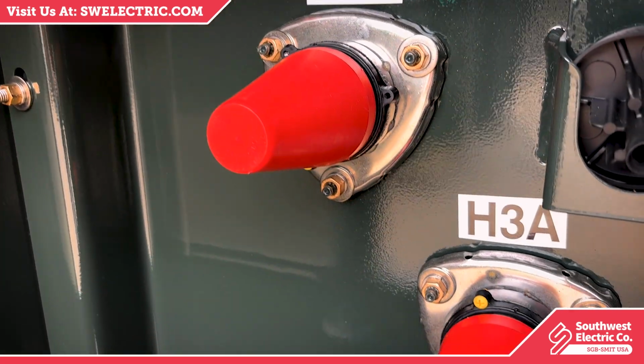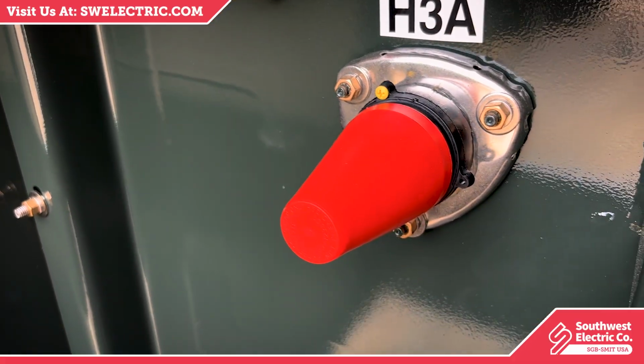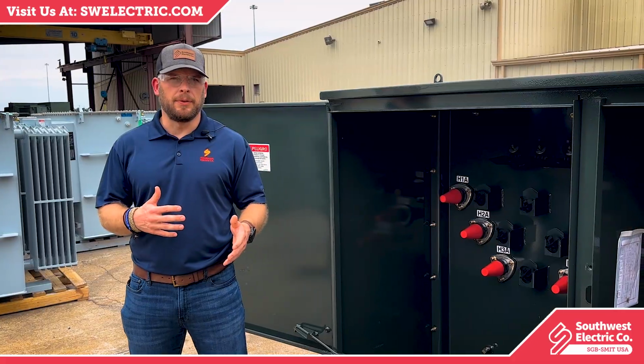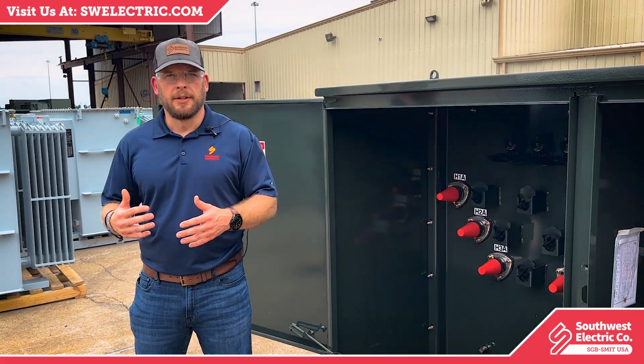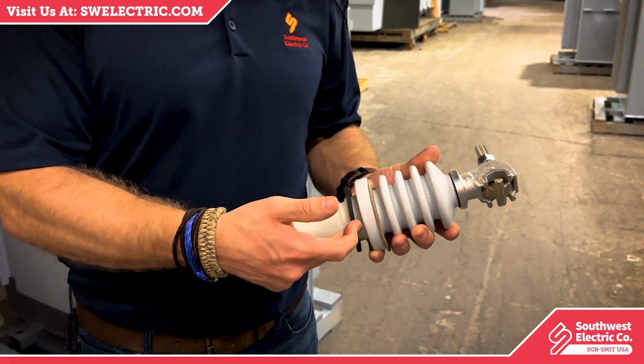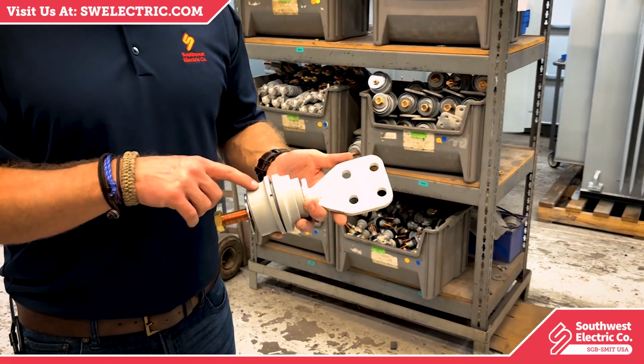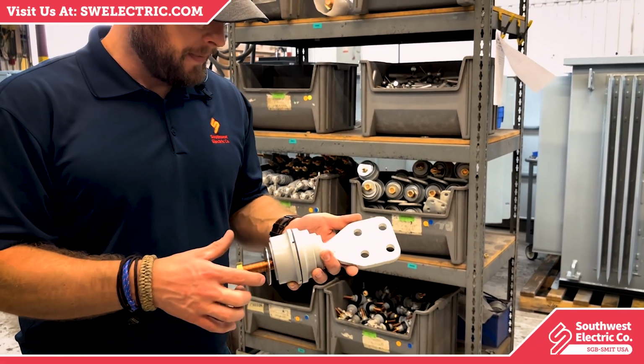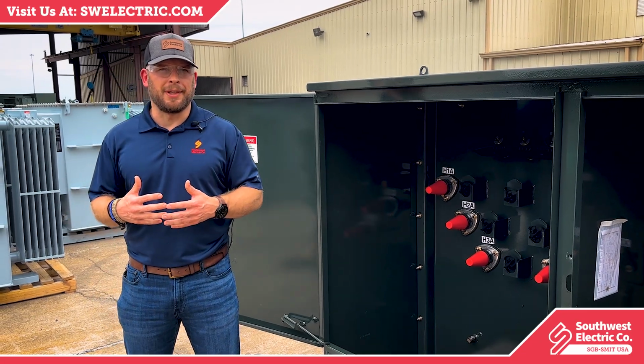The bushing contains a metal conductor, typically made of copper or aluminum, which carries the current into or out of the transformer windings. Surrounding that conductor is a layer of insulation, such as porcelain or epoxy. This insulation ensures that the current doesn't arc or discharge to the tank.